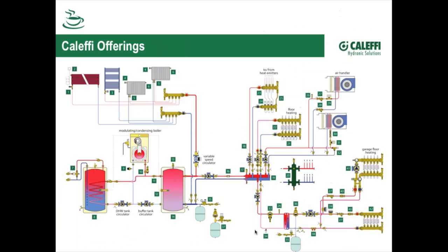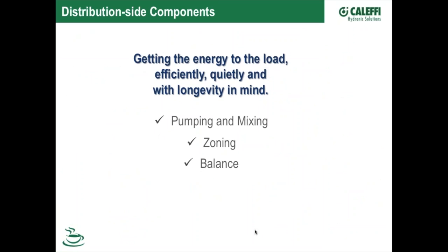So what we have to do now is pump the fluid around through the circuit. We might have to mix different temperatures or multiple temperatures. We might have a job where we've got to have zoning, where we want to turn different circuits or different areas of the building on and off. And we want to balance the system. We want to make sure that every zone in the building or every heat emitter in the building has just the right amount of flow that it needs to do the job, and that's where a balancing component would come into it.